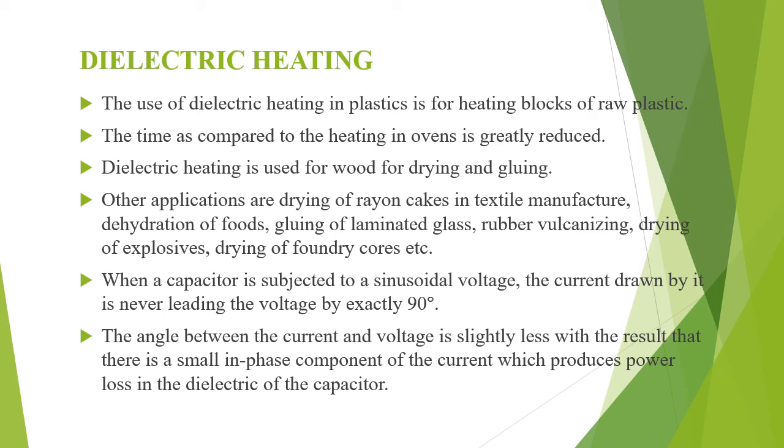The principle of dielectric heating. When a capacitor is subjected to a sinusoidal voltage, the current drawn by it is not leading the voltage by exactly 90 degrees. This is because there is a small in-phase component of current which produces power loss in the dielectric of the capacitor. At an ordinary frequency of around 50 Hz, this loss may be small enough to be negligible. But at high frequencies, this loss becomes large enough to heat the dielectric. This loss is what is used in heating the dielectric.